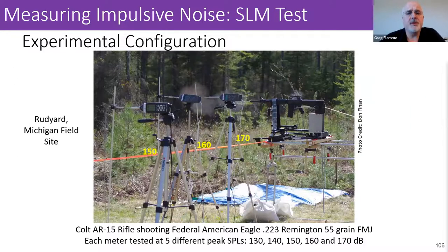Don't want to spend a huge amount of time on this, but our group did spend some time a few years ago comparing various sound level meters to a lab standard or a more standard measurement system at multiple sound levels. What's pictured in the photograph is an AR-15 mounted onto a gun stand. And we positioned the sound level meter plus a parallel microphone for the lab standard system at sound levels of 170, 160, 150, and so on all the way down to 130, just to see what the comparison was across these devices and relative to a proper system.